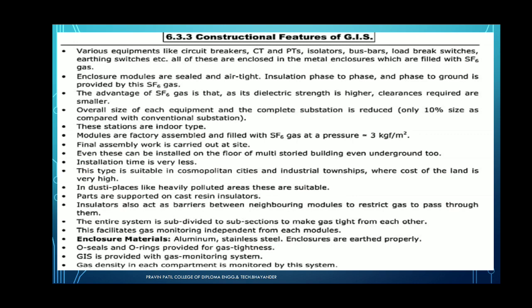I repeat again the construction features of the gas insulated substation one by one. The various equipment like the circuit breaker, current transformer, potential transformer, isolator, bus bar, load break switches, earthing switches, these all are enclosed in the metal enclosure which is filled with the SF6 gas. Enclosed modules are sealed tight and insulation phase to phase. Phase to ground is provided with the SF6 gas.